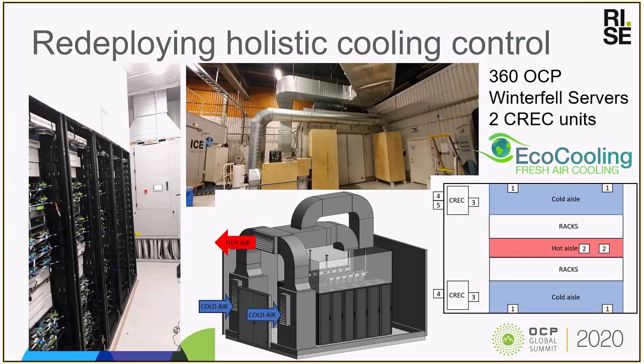So, redeploying this holistic cooling control, with the support of EcoCooling we have built one of our modules in RISE, which is in Luleå, the Research Institute, the ICE data center. We have kitted it out with 360 OCP Winterfell servers, a later generation of OCP server. We've used the same cooling units as in Boden, so we have two direct fresh air cooling units. This is a room within a room, so the outside air from the larger facility is ingested through the coolers into the data center here.